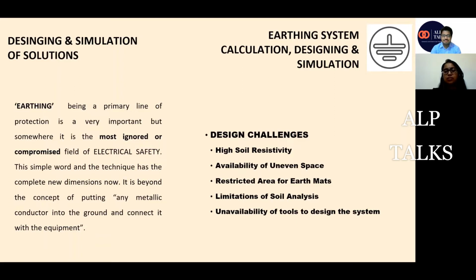Yeah. So basically, first of all, we'll discuss the earthing system. Traditionally, there was not so much awareness about the earthing system, but people thought that any metallic conductor can be buried into the ground and connected to the equipment, and it will carry our fault current and protect my equipment. Obviously it will work, because it is a metallic conductor, so it will carry the fault current into the ground, but it cannot always be helpful. Maybe for good soil resistivities, like if the soil resistivity at a location is 10 to 20 ohm meters, it is possible that burying any metallic conductor, whether GI or cast iron, can work.